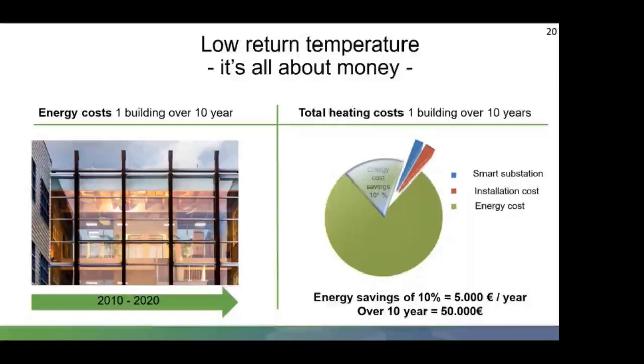By decreasing the temperature of the primary return, the heat losses are reduced to a minimum, and the heating system is optimized to its maximum, so it's working as efficiently as possible. It's like in a car, going along the motorway at 56 miles an hour. I know it's not always the best way to do it, but it's as efficient as possible. You'll get the best out of the district heating and condensing boiler heat source, but only if you come back at low return. You're all familiar with condensing boilers, and they want that low return temperature to work properly.